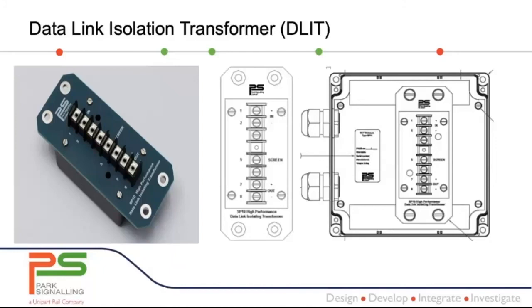Now, electrified areas, as I mentioned before, 25 kV, can cause further issues through electromagnetic interference. In 25 kV AC areas, it's been common practice to use traction return earths rather than a separate earthing system. This is for safety reasons, or there might be no alternative, for example, if you're installing over a viaduct. So the effect of this 50 Hz interference can degrade components of the SPU due to constant stress, and that results in them becoming less effective as protection devices. And that can then lead to other problems with data corruption.